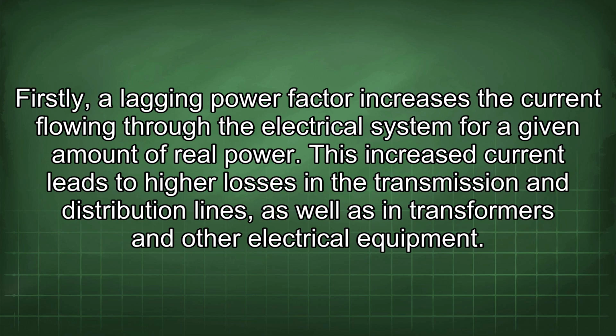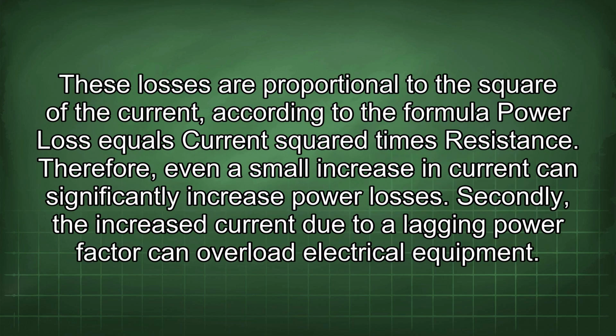This increased current leads to higher losses in the transmission and distribution lines, as well as in transformers and other electrical equipment. These losses are proportional to the square of the current, according to the formula power loss equals current squared times resistance. Therefore, even a small increase in current can significantly increase power losses.